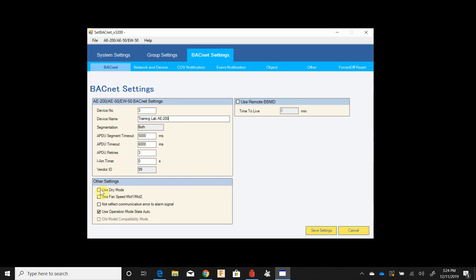Dry mode will enable the selection of the dehumidification or dry mode which does not control to humidity, it just tries to suck moisture out of the air. Up here in the northwest we don't use this so I leave that box unchecked. Fan speed mid 1 and mid 2 are partial fan speeds applicable to certain units. I just generally leave that off to not reflect communication error to alarm signal. If there's a comm error I want to see it on the front end.